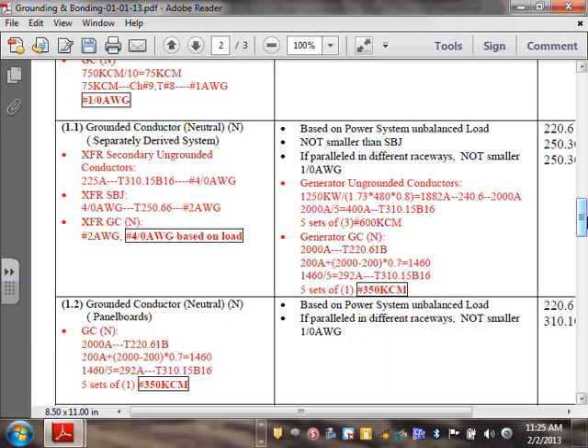Identical. But typically what I wrote here, guys, number 4, is based on the load. Typically at this level of voltage, when I do sizing, I say if you have 300 amps or less, full neutral, because we have a lot of lighting panels and receptacle panels, and almost all of them have harmonic loads, right? And they also have a lot of loads. Now when you go higher than 300 amps, most likely you're dealing with air handling units and chillers and all this good stuff. Then you start derating. The code allows us to derate anything higher than 200 amps, right? And on neutral load, you start cutting it by 70%. So I always say 300 amps full neutral is a very good idea design-wise.